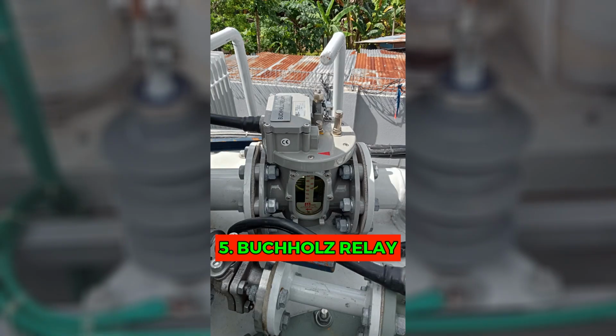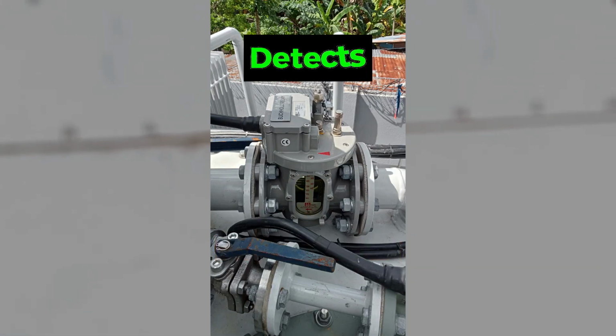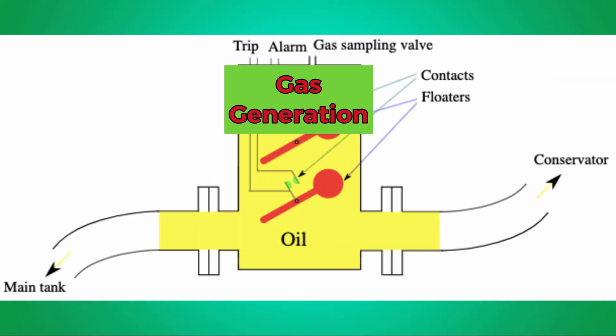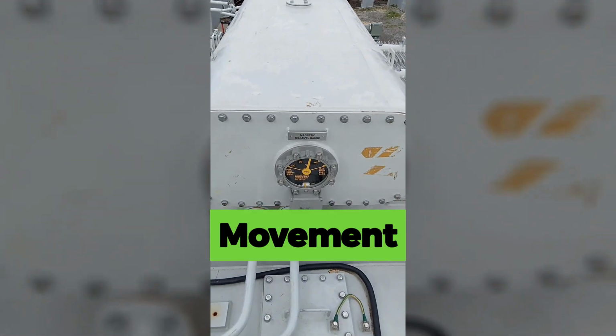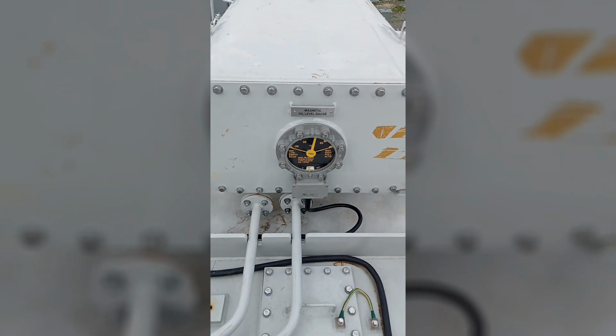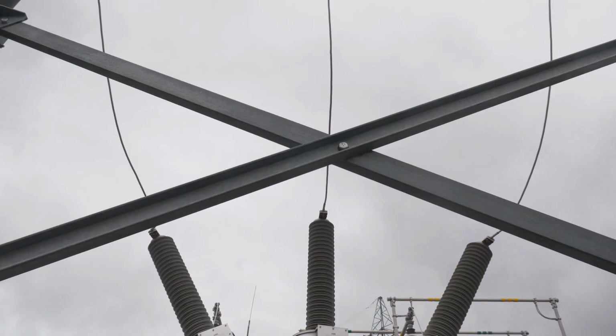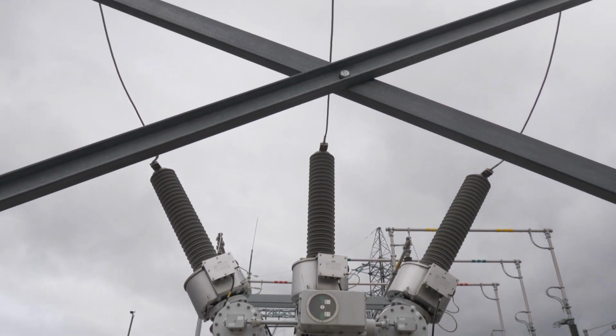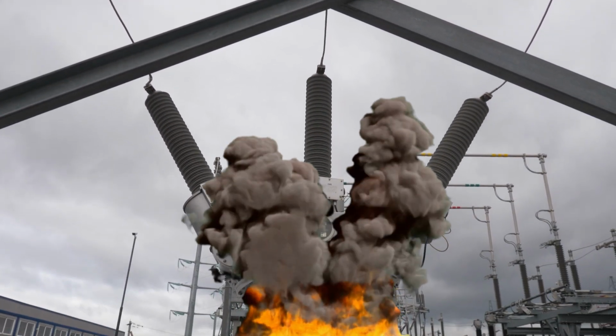The Buchholz relay. This clever device detects internal faults within the transformer. It works by sensing any sudden gas generation or oil movement, which can indicate the presence of a fault. When triggered, it initiates an alarm or a trip signal, protecting the transformer from further damage.